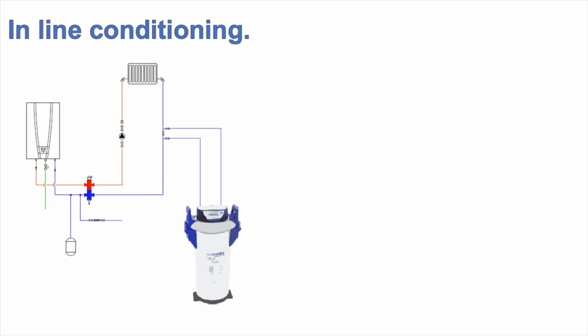We've got a good base to start with, and essentially what we're going to do is we're going to use either a separate pump or the system pump, if it can create enough flow and the pressure to circulate the existing water around the system through the Clarimax and back out. We can monitor what's going into the Clarimax by using the combo meter. It also registers the amount of litres we've used, and then the outgoing, we just use a simple traffic light system on the front of the Clarimax itself.